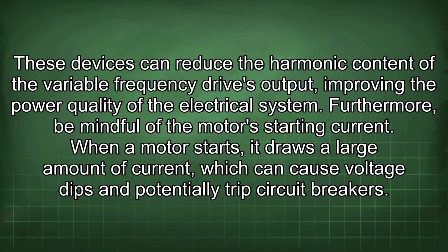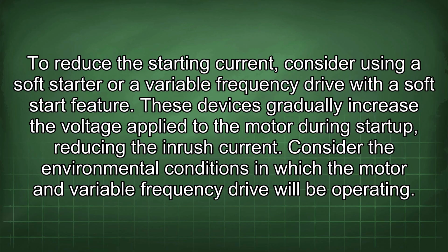Furthermore, be mindful of the motor's starting current. When a motor starts, it draws a large amount of current, which can cause voltage dips and potentially trip circuit breakers. To reduce the starting current, consider using a soft starter or a variable frequency drive with a soft start feature. These devices gradually increase the voltage applied to the motor during startup, reducing the inrush current.